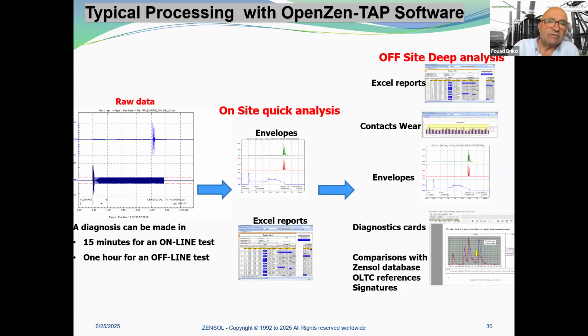When you have recorded these raw data, the software immediately calculates the envelopes and produces an Excel report. With the dark blue here, the software brings you to some tests, and then you analyze the signals. This is the on-site quick analysis. For off-site deep analysis, we use the Excel reports. Thanks to the high and low frequency envelopes, we are able to detect contact wear. We analyze the envelopes, and we also have a database where we compare with the OLTC reference signatures.